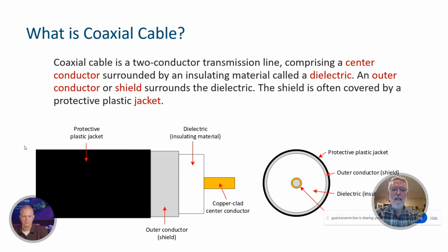Moving left to right in the leftmost figure, we've got the outer conductor or shield, then the dielectric, which is an insulating material, and then the center conductor, which the vast majority of the time in the cable industry is copper clad, either steel or aluminum. In the case of subscriber drop cable, it's copper clad steel, and in the case of hardline cable, it's copper clad aluminum. There is solid copper center conductor available for certain applications, but for most of what we deal with in the cable industry, it's really not necessary, because skin effect keeps most of the RF at and near the surface, as we discussed in a previous session on skin effect and skin depth. So that extra copper, at least from an RF perspective, if you went with a solid copper center conductor, isn't really going to buy you any benefit.